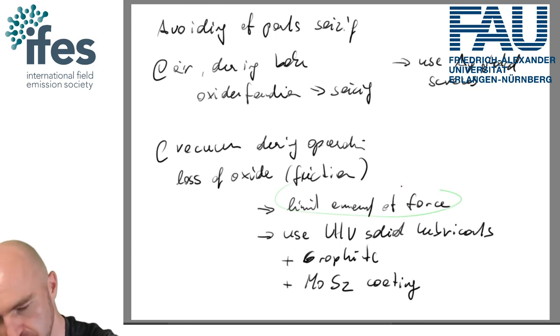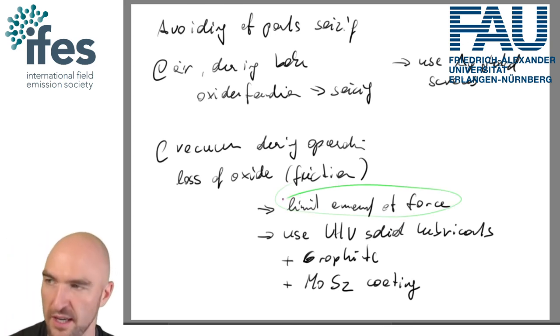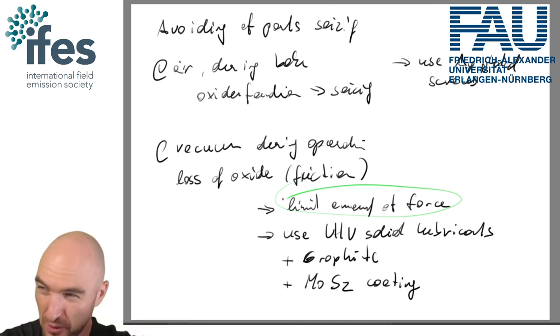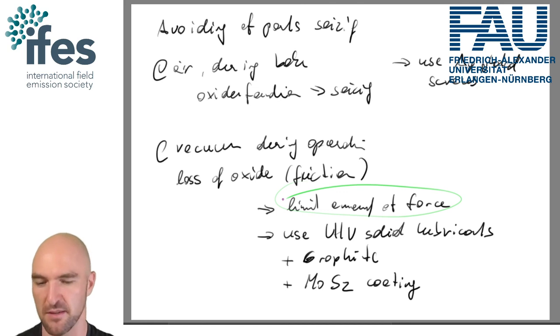But if you can, just limit the amount of force that parts experience. So if you have something where you need force in an ultra high vacuum system, it's probably going to seize up at some point, unless you can lubricate it very well.